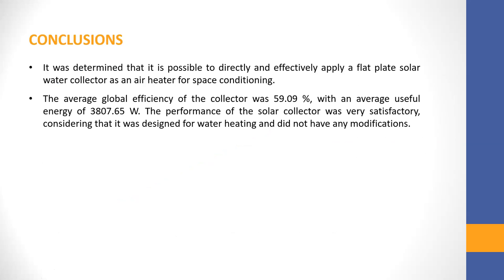Conclusion. It is determined that it is possible to directly and efficiently apply the flat-plate solar water collector as an air heater for space conditioning. The global efficiency was 59%. The performance of the solar collector was very satisfactory considering that it was designed for water heating and did not have any modification.